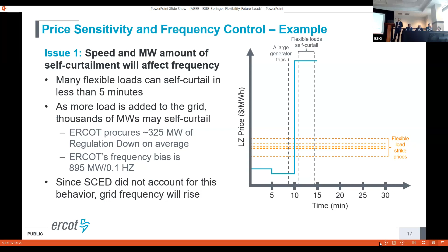Just for some context, our frequency bias is about 1,000 megawatts per tenth of a hertz. So every 1,000 megawatts that comes off, we could expect up to a tenth of a hertz frequency rise. Right now ERCOT is only procuring about 325 megawatts of reg down on an average day, so this is going to far exceed any frequency regulation control we've got. So just by definition, we expect the frequency to rise.